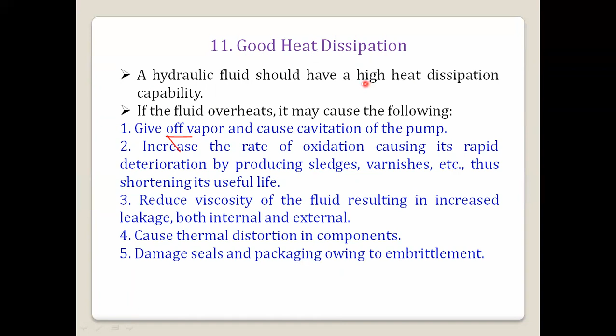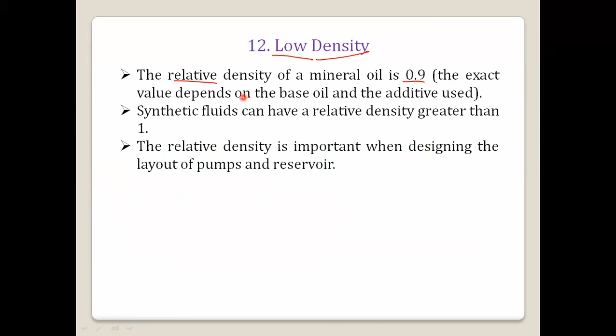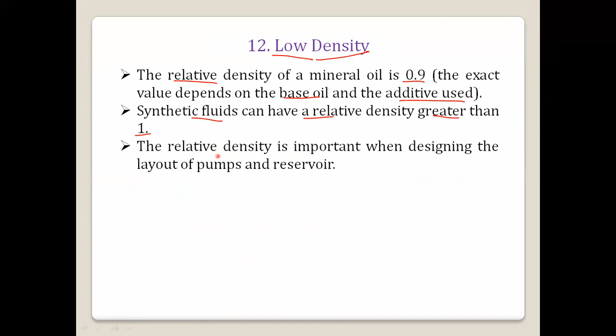Then coming to the density, we should have low density. The relative density of a mineral oil is 0.9, and the exact value depends on the base oil and the additives used. Mineral oil is a combination of petroleum oil and additives, and we use additives to improve the properties. Synthetic fluids can have a relative density greater than 1, while for mineral oil it is around 0.9. The relative density is very important when designing the layout of the pumps and reservoir.